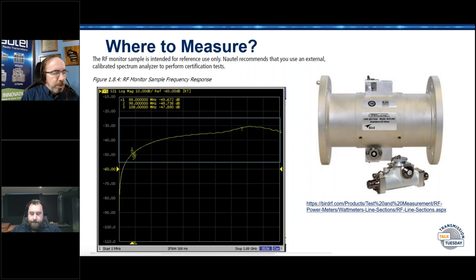William asks how often they need to be calibrated, and I'm not sure if we're talking specifically about the through line section or the analyzer, but the short answer is we've got our gear on a 1 year, 2 year calibration schedule, something like that. We've got different calibration schedules for different pieces of gear depending on the type of use.